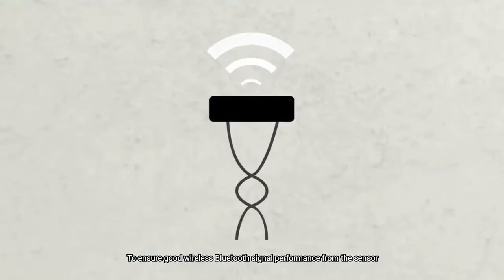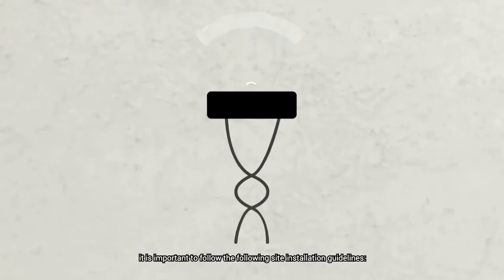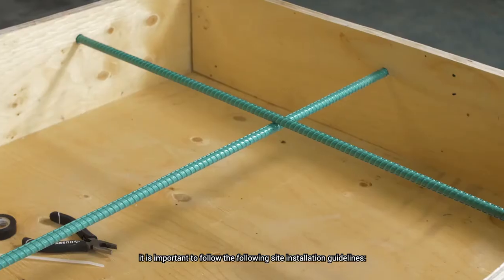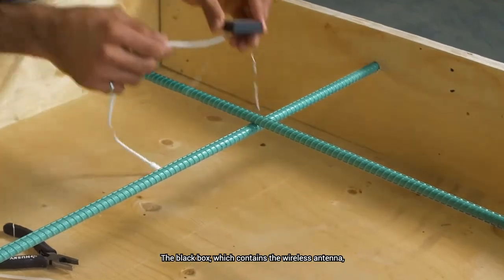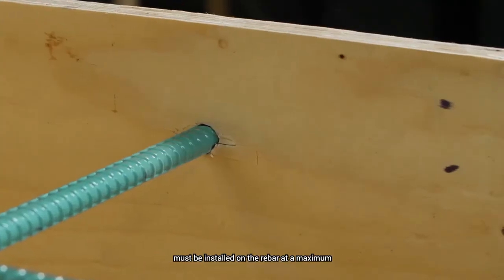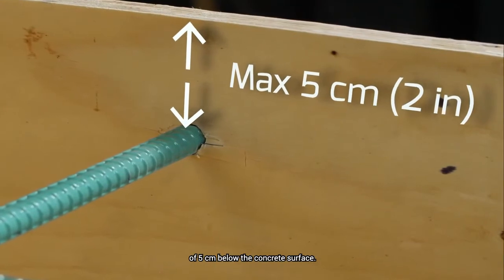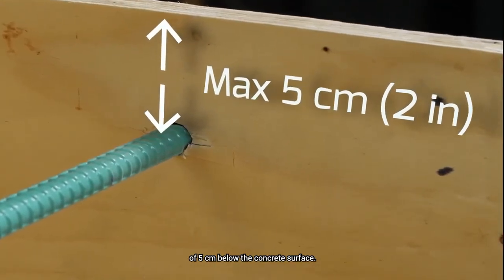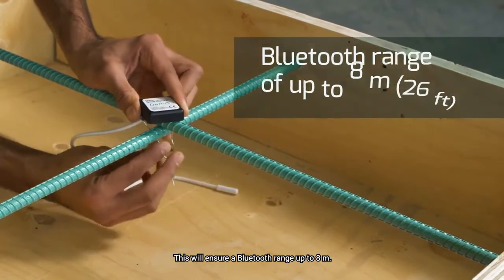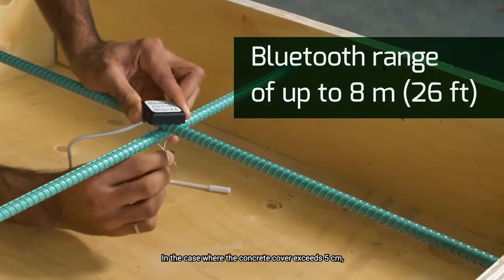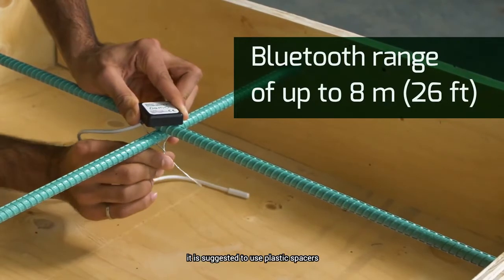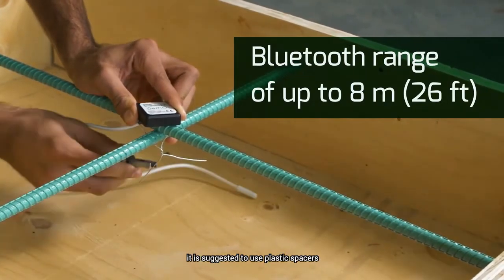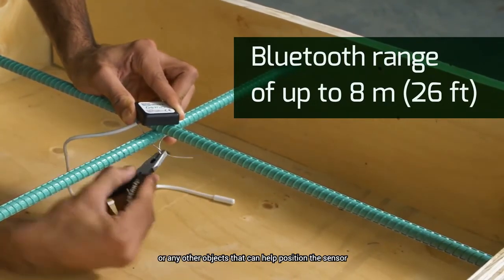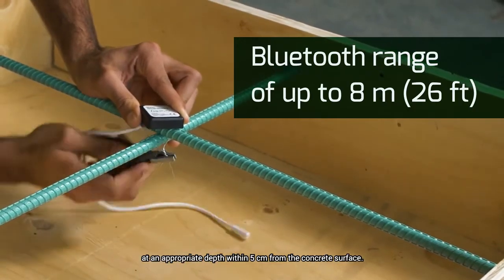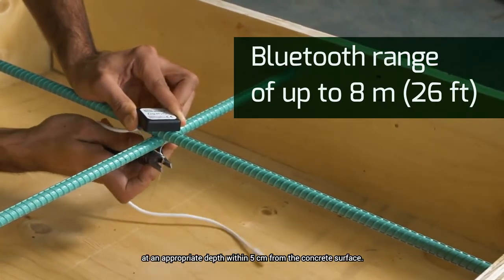To ensure good wireless Bluetooth signal performance from the sensor, it is important to follow the following site installation guidelines. The black box, which contains the wireless antenna, must be installed on the rebar at a maximum of 5 centimeters below the concrete surface. This will ensure a Bluetooth range up to 8 meters. In the case where the concrete cover exceeds 5 centimeters, it is suggested to use plastic spacers or any other objects that can help position the sensor at an appropriate depth within 5 centimeters from the concrete surface.